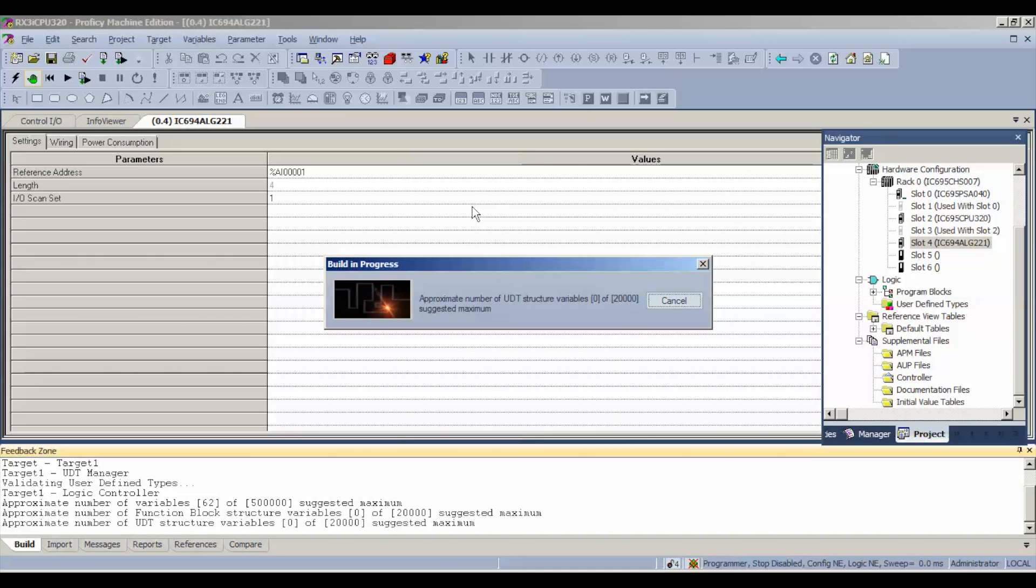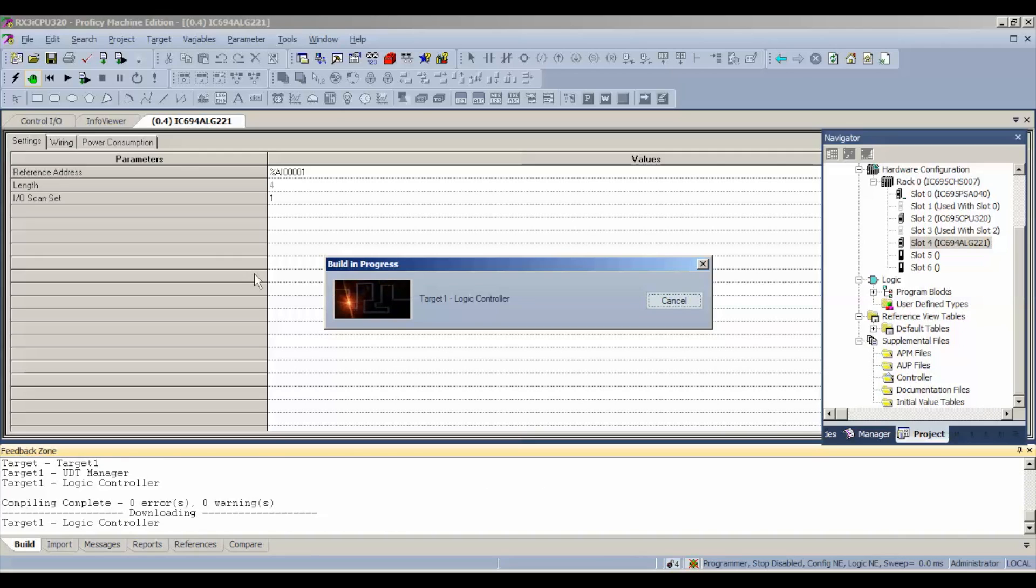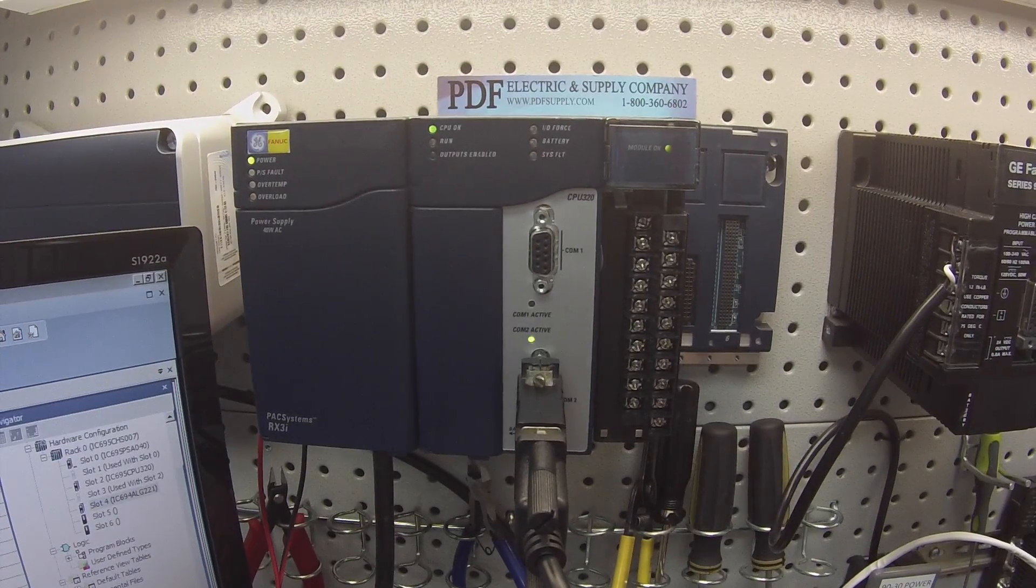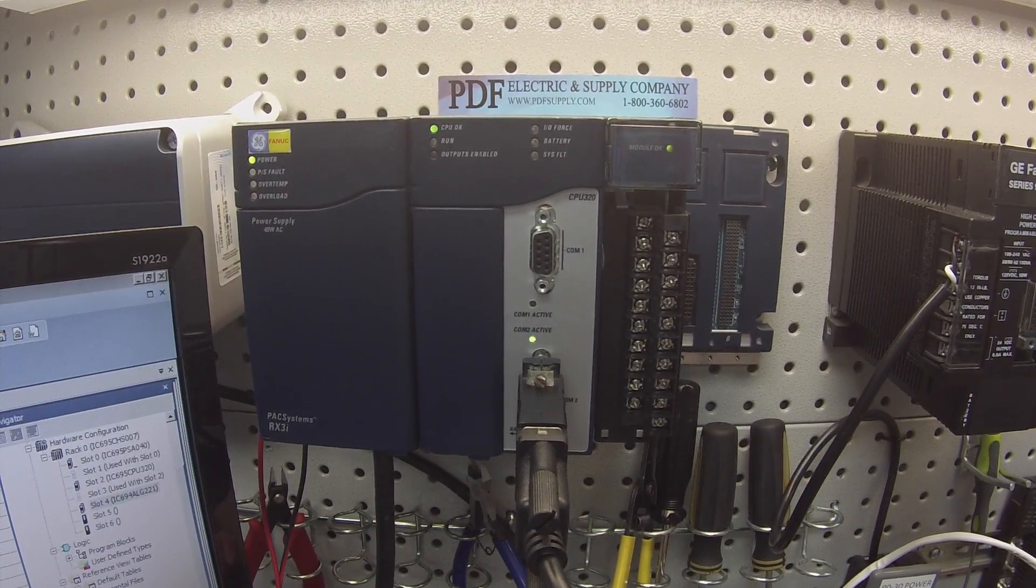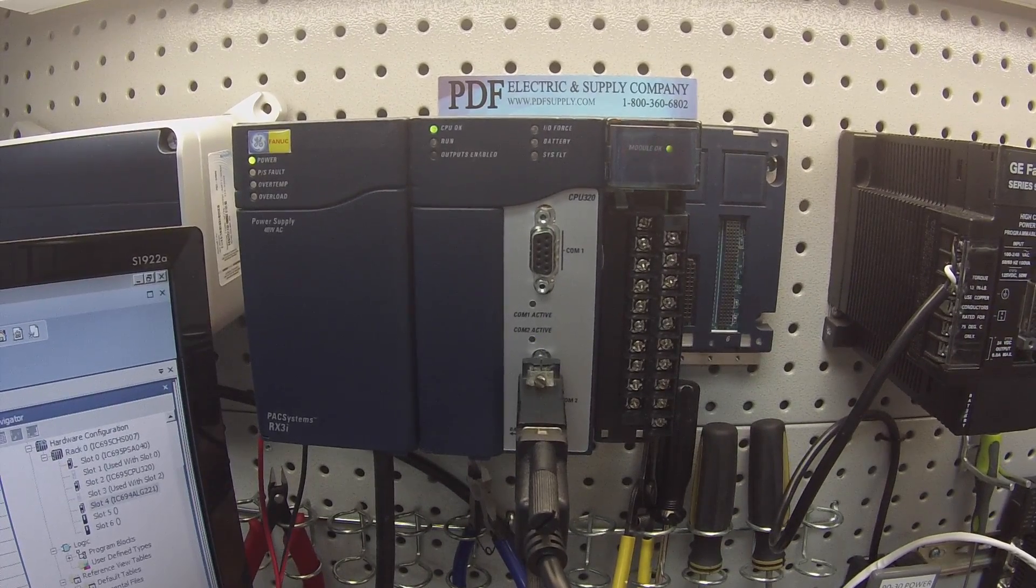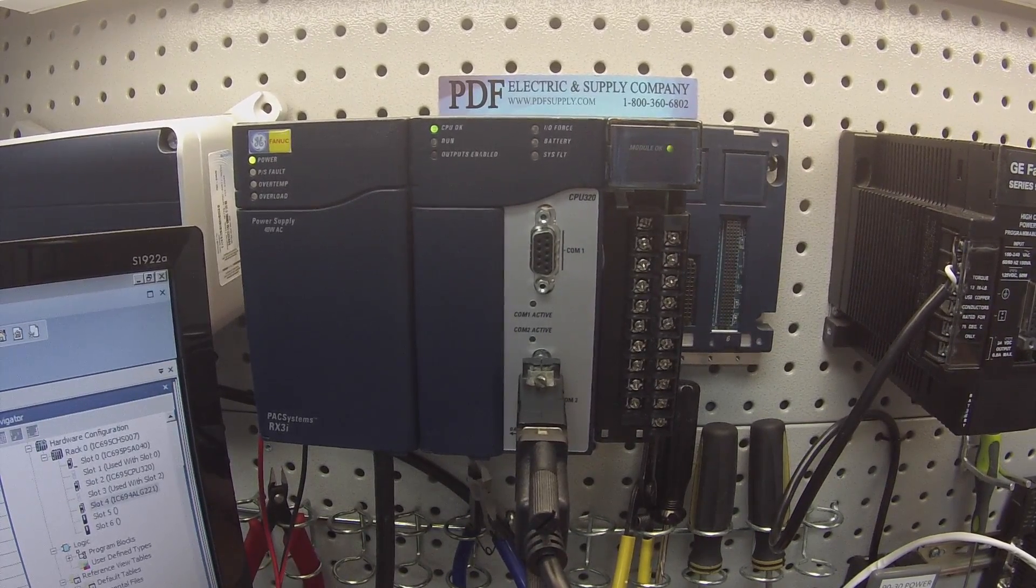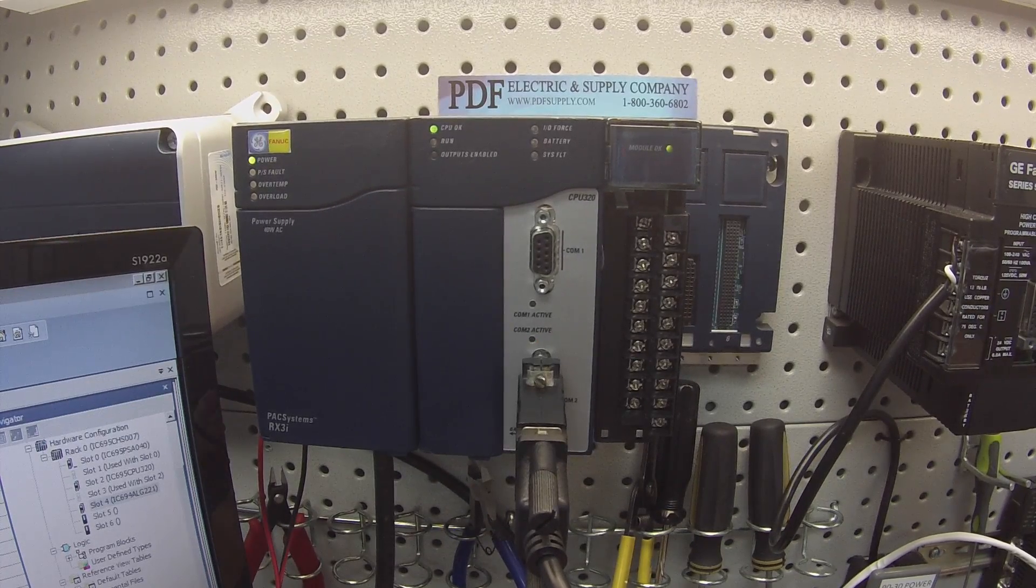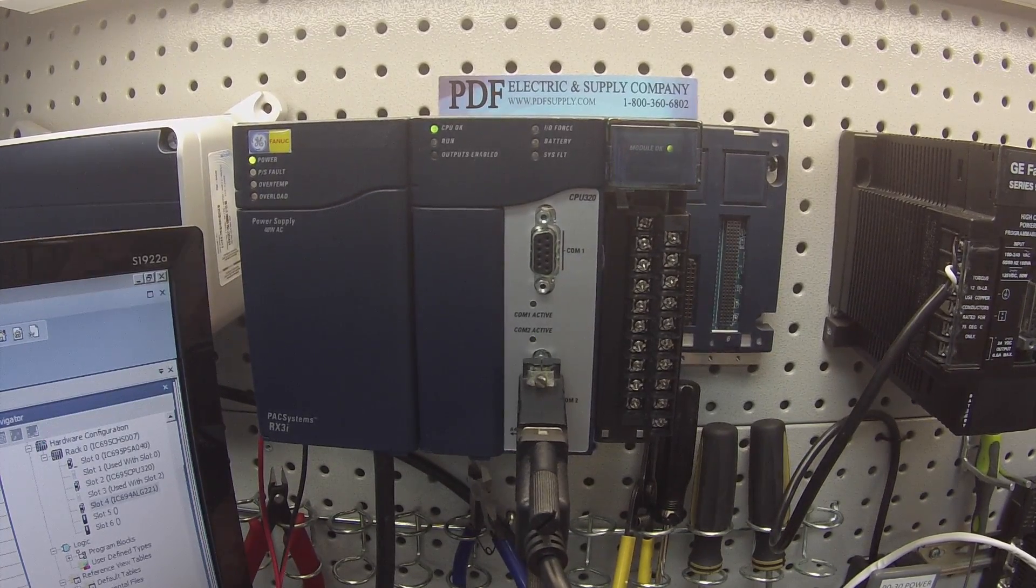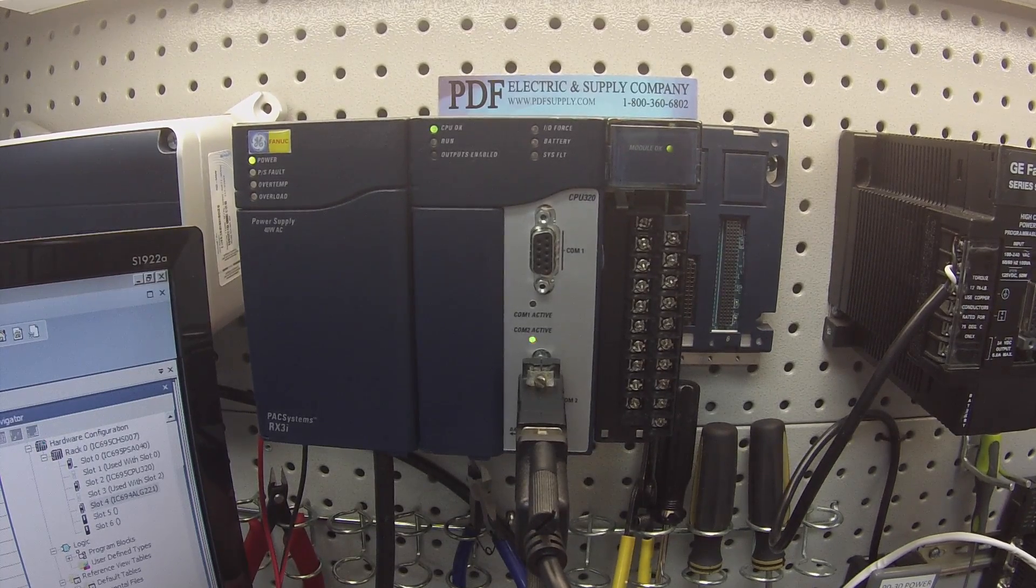We want to download hardware configuration, motion and logic, which is the top two selections. Another thing that I have while this is downloading that I'm going to be using is a 4 to 20 milliamp output generator. It's a fully adjustable generator, meaning that I can dial up and down the amount of current that it's giving me, the amount of milliamps. The reason that's good is because we'll be able to test the range and resolution of each channel.